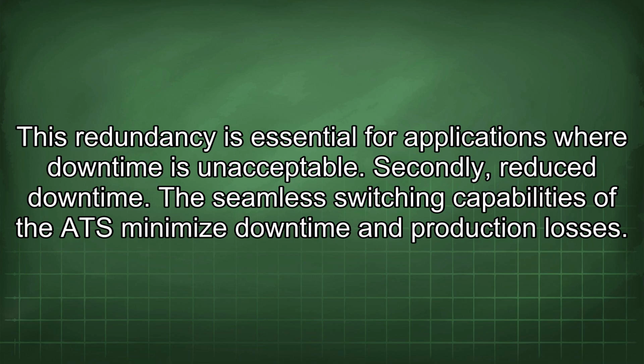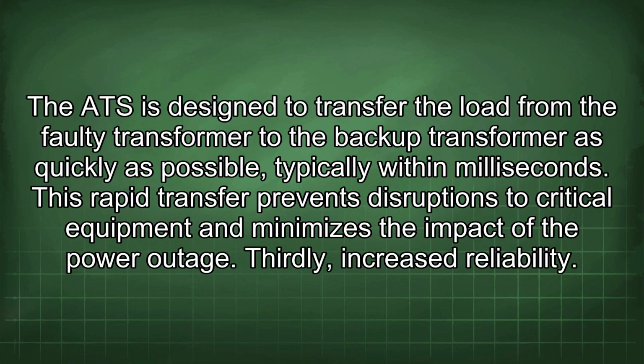Secondly, reduced downtime. The seamless switching capabilities of the ATS minimize downtime and production losses. The ATS is designed to transfer the load from the faulty transformer to the backup transformer as quickly as possible, typically within milliseconds. This rapid transfer prevents disruptions to critical equipment and minimizes the impact of the power outage.